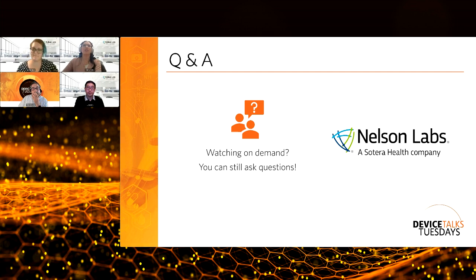I would add to that that there are known cytotoxic agents or known irritants. And the thought would be, as engineers, that when you're investigating these materials, you're looking for performance for the device, but you're also looking for what's known about that material. And this is an assumption on my part. If it's not included in the processes, there should be some sort of evaluation of what's known about the material in its solid state, how you will use it, or in its liquid state, whatever phase you're using it in, to be thoughtful there. So we know that you don't want to get to the end and say, oh my goodness, now we finally tested it and we're failing every single test.